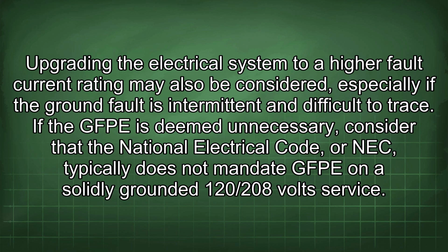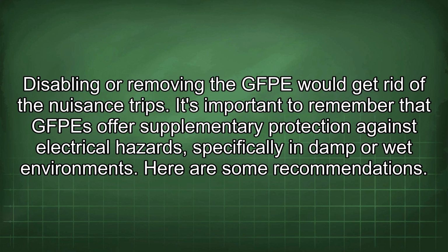If the GFPE is deemed unnecessary, consider that the National Electrical Code, or NEC, typically does not mandate GFPE on a solidly grounded 120/208 volt service. Disabling or removing the GFPE would get rid of the nuisance trips. It's important to remember that GFPEs offer supplementary protection against electrical hazards, specifically in damp or wet environments.